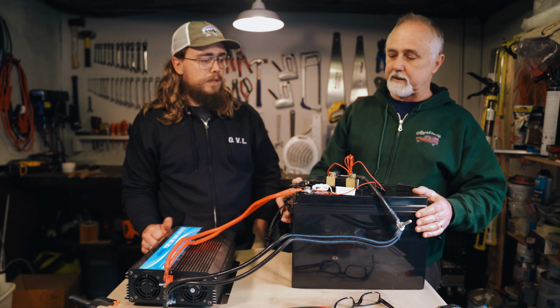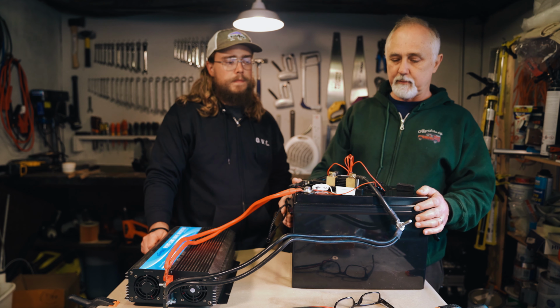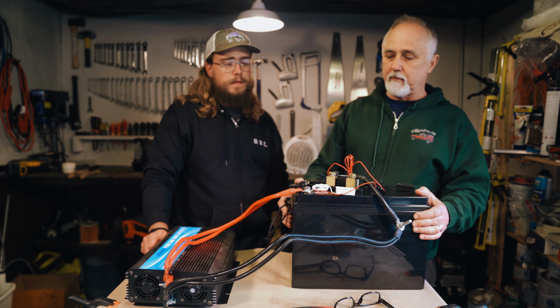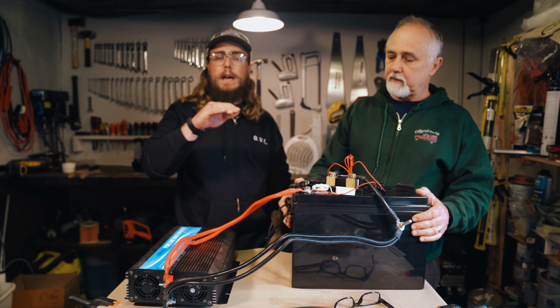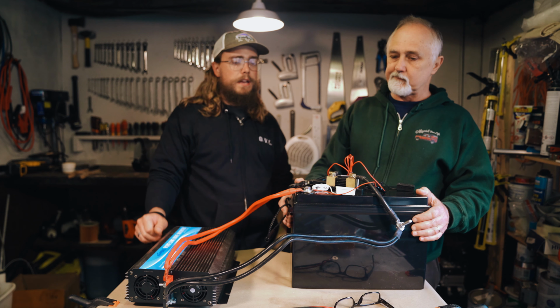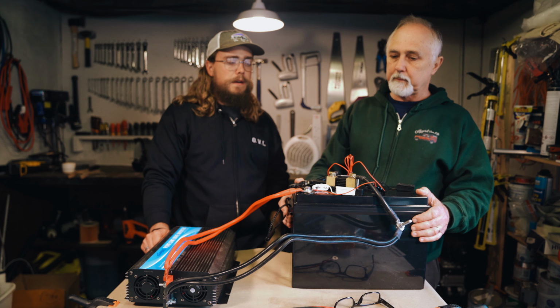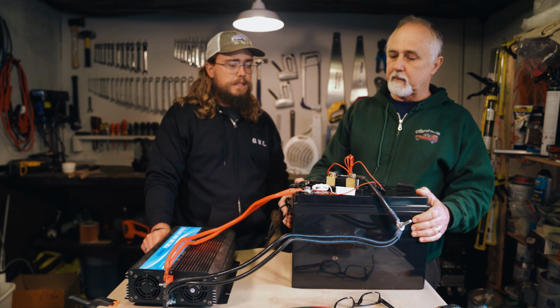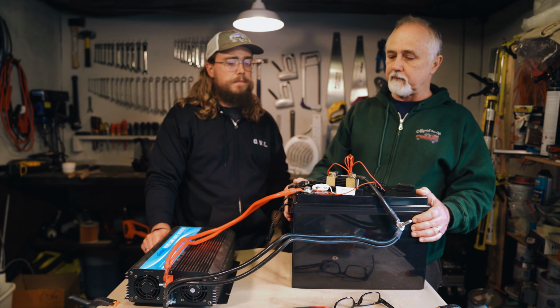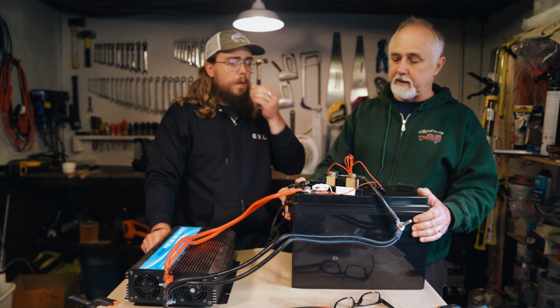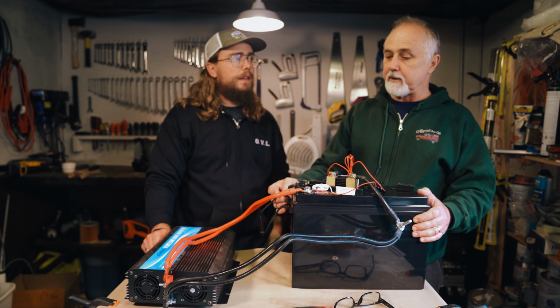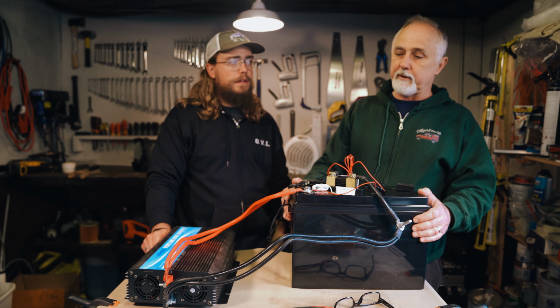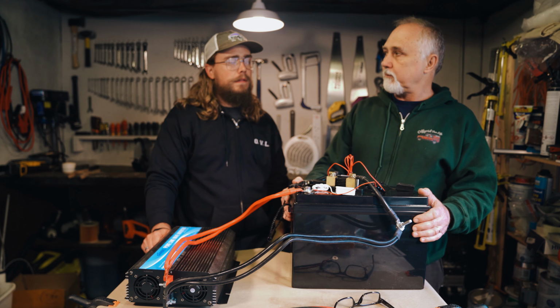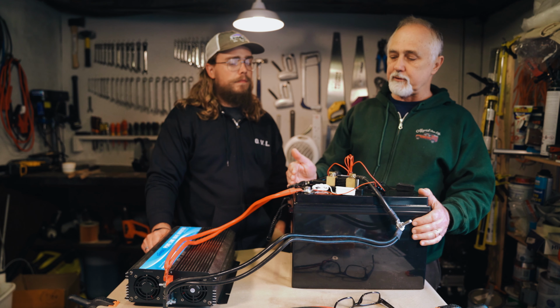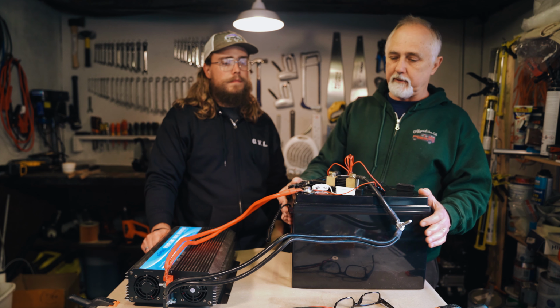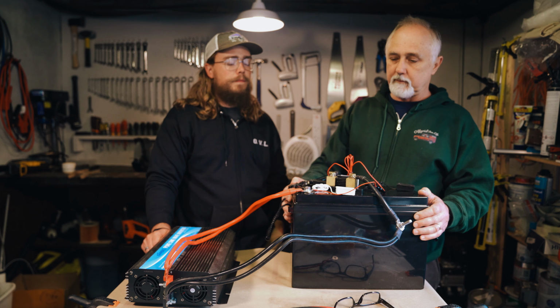The cells reached capacity. The heat build-up in here was quite acceptable, not a problem. Once we were running below the threshold of the BMS, at 80 amps draw, it was sitting at around 40 degrees Celsius inside the cells. And 80 amps is a high draw, make no mistake - that's not Mickey Mouse, that's doing a lot. Running a 1 kilowatt heater for a few hours at that, and the temperature stayed around 40 degrees centigrade - quite acceptable.